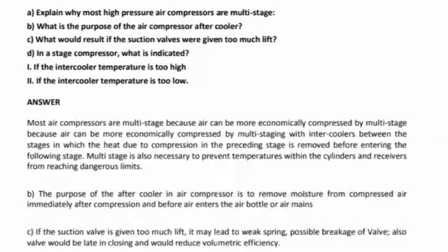The aftercooler is fitted at the air outlet of the final stage delivery of the air compressor to remove moisture from the compressed air immediately after compression before the air enters into the air bottle or the air main system. If the suction valve is given too much lift, it may lead to weak spring, possible breakage of the valve, and also the valve would be late in closing and would reduce volumetric efficiency of the air compressor.